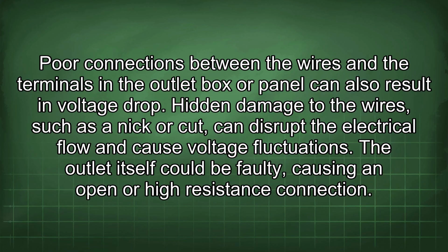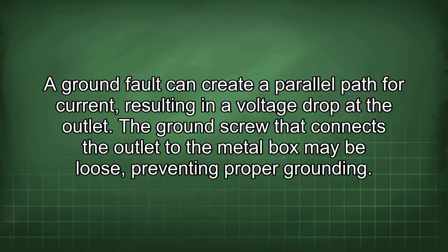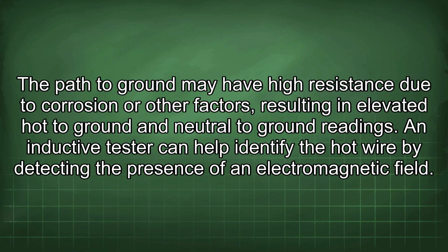Hidden damage to the wires, such as a nick or cut, can disrupt the electrical flow and cause voltage fluctuations. The outlet itself could be faulty, causing an open or high resistance connection. A ground fault can create a parallel path for current, resulting in a voltage drop at the outlet. The ground screw that connects the outlet to the metal box may be loose, preventing proper grounding. The path to ground may have high resistance due to corrosion or other factors, resulting in elevated hot to ground and neutral to ground readings.